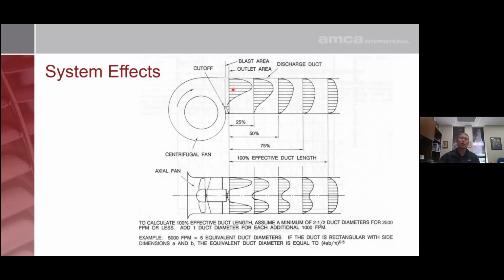this picture here, static pressure regain is very important if you want efficiency of the unit and you want the fan performing at its best. If you don't allow for static pressure regain, basically you're going to lose velocity pressure at the fan discharge. And velocity pressure is simply your velocity divided by 4005, that quantity squared. And so if you're moving air at 4,000 feet per minute, you're going to lose 1 inch of static pressure by not allowing for static pressure regain.